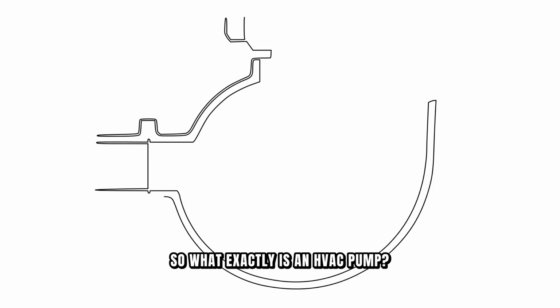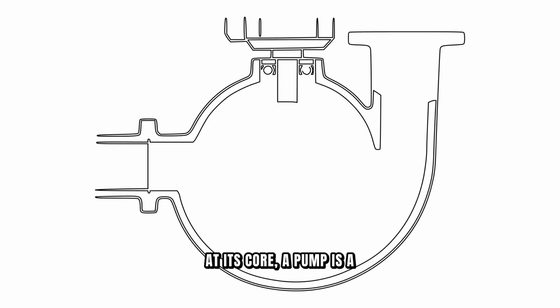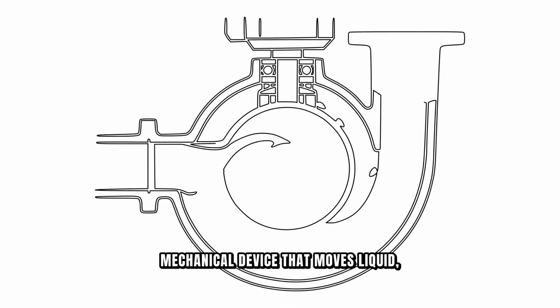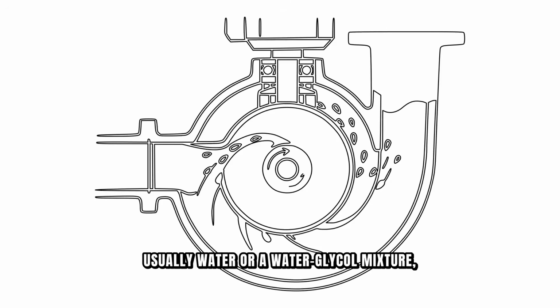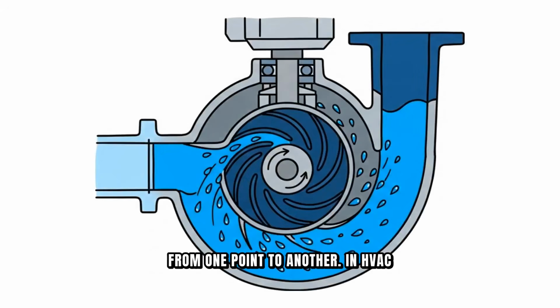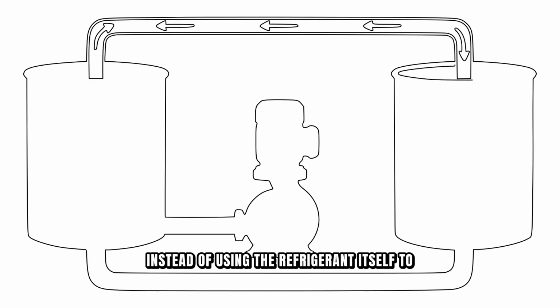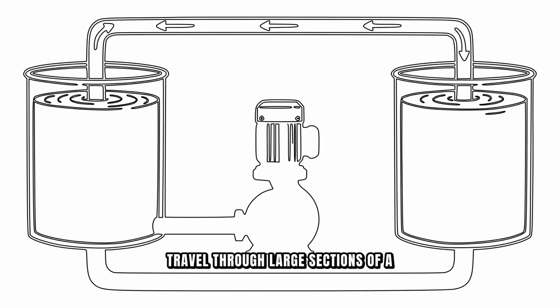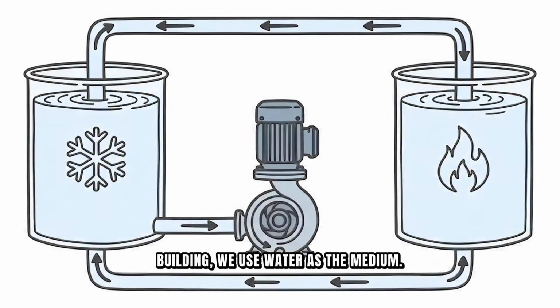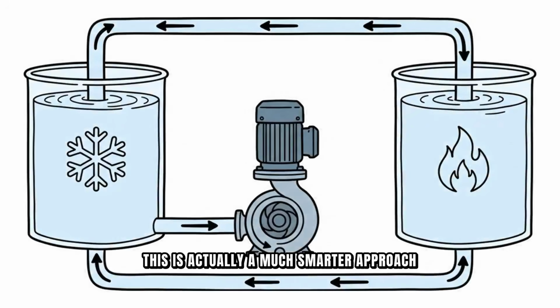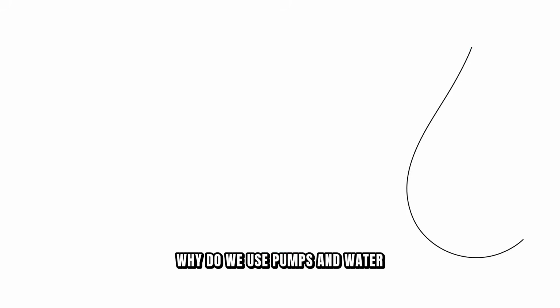So what exactly is an HVAC pump? At its core, a pump is a mechanical device that moves liquid, usually water or a water glycol mixture, from one point to another. In HVAC systems, pumps circulate water through pipes to absorb or reject heat. Instead of using the refrigerant itself to travel through large sections of a building, we use water as the medium. This is actually a much smarter approach than you might think.